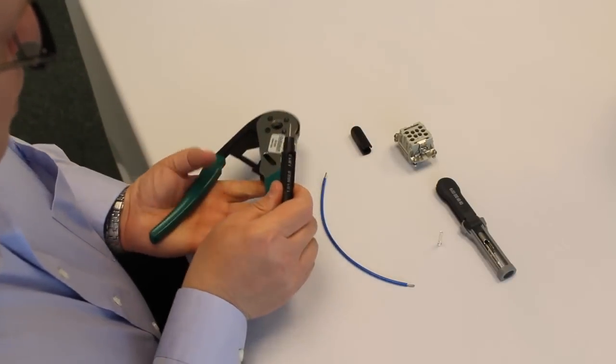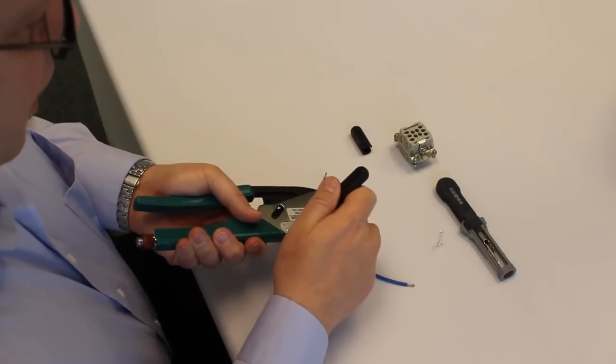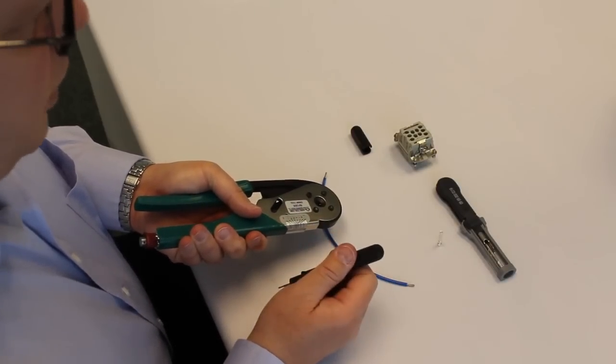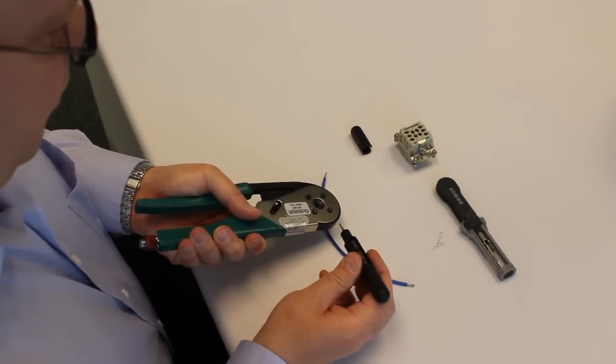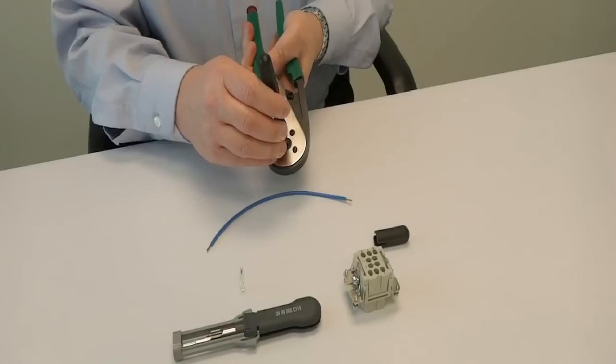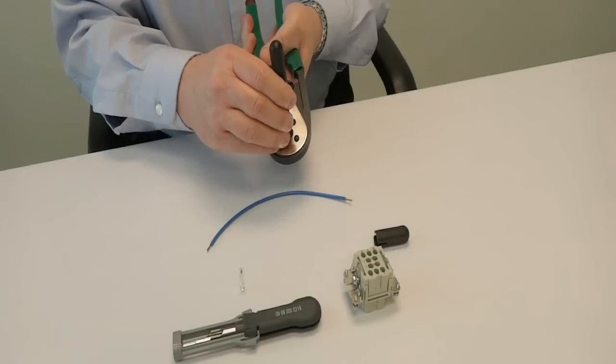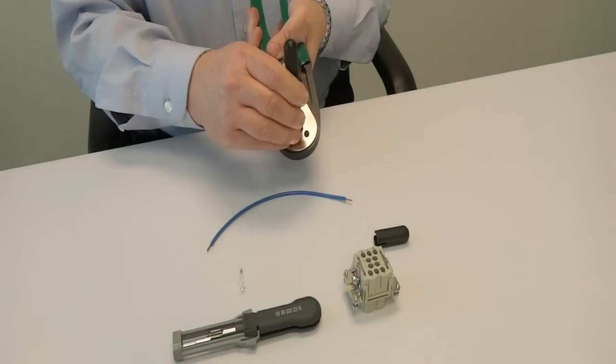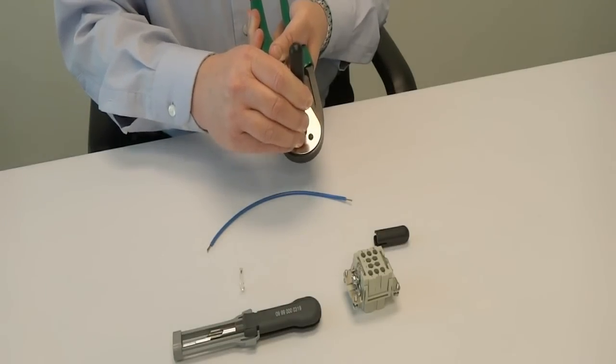To adjust the tool, simply close it to have the indenters closed. This tool has four indenters. It's called a four indenter crimp. And then we can insert the gauge in between the four crimp jaws to check and see how well the tool is adjusted.